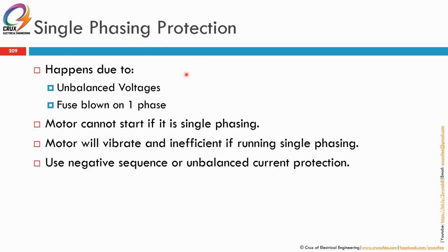Single phasing protection. It happens due to unbalanced voltages and fuse blown on one phase. So these are the typical cases. If you know, 1% unbalanced voltage can produce about 6% unbalanced current, or the negative sequence current. So if the motor is going to be started with a single phasing condition, it can never start because it doesn't have enough torque to turn the motor. But if the motor was running and suddenly it lost one of its phases, it will continue to run, but it will have very high vibration, and it will be very inefficient running under single phasing condition. So how can we detect this? We use negative sequence or unbalanced current protection.